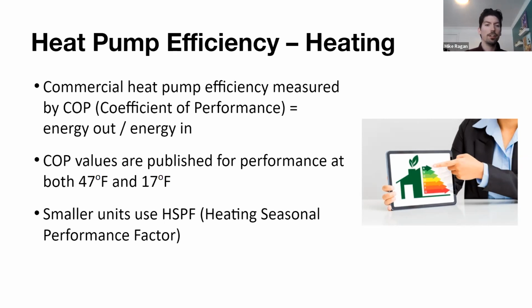So in terms of COP efficiency publications, COP is oftentimes measured for performance at 47 degrees and 17 degrees, which is just a way of taking a look at what a heating output looks like in your shoulder season months, maybe your April months in the New England weather, or hopefully we're getting there sooner than then for 47 degrees. But you're also looking at 17 degrees, a very common wintertime heating temperature. Now, you can calculate COP values for other temperatures as well. If you're curious what your COP is going to be at 0 degrees, perfectly fine. You would just need to go into your respective manufacturer's engineering manual and take their published information and do that manual calculation.